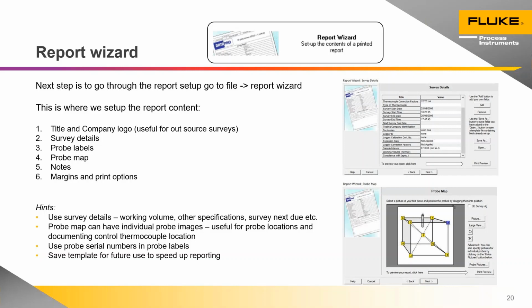So the first stage is to enter survey details. And some of those boxes are automatically filled, as you can see on the screen here. So start dates, start times, but there are boxes on there that you would need to fill manually. Our advice would be that the next survey due date would be a very good thing to fill in this box. As would the working volumes or work zone dimensions. You can see it's the second box from the bottom there within the survey details.